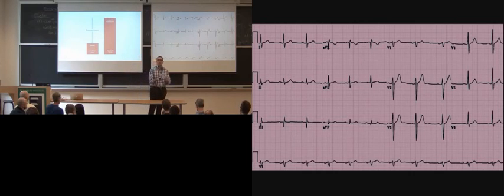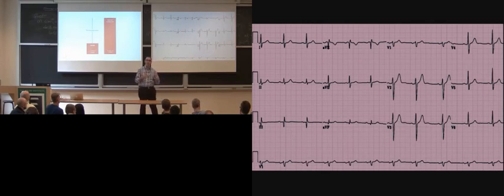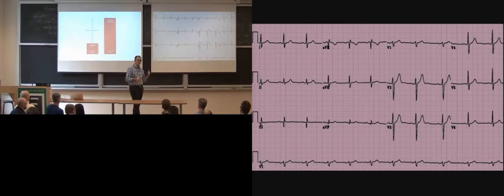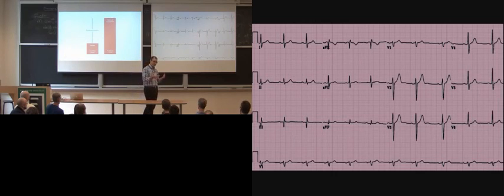When medical learners are taught to interpret ECGs, the first rule is ignore everything the machine says. The reason why is the algorithms, though they're really good at identifying normal, anything that's abnormal can be misinterpreted, and the machines are typically unreliable. Often this is not a piece of hardware that is replaced very frequently or updated ever. The machines that I use to get the ECGs for the patients that I look after could be 20 years old and are using the algorithm that's built into the machine.